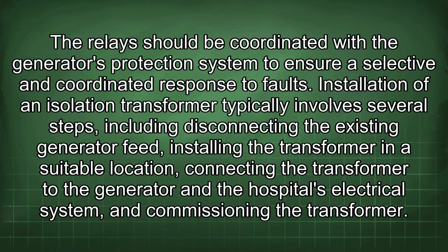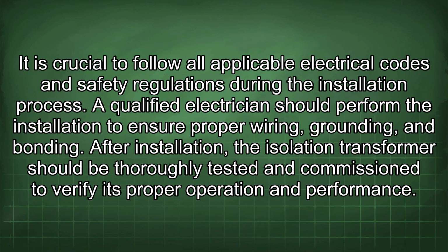Installation of an isolation transformer typically involves several steps, including disconnecting the existing generator feed, installing the transformer in a suitable location, connecting the transformer to the generator and the hospital's electrical system, and commissioning the transformer. It is crucial to follow all applicable electrical codes and safety regulations during the installation process. A qualified electrician should perform the installation to ensure proper wiring, grounding, and bonding.